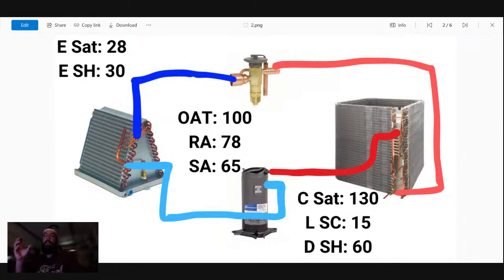It could also be some kind of trash or debris getting into it. Now we have a screen that should correct for that, but stuff still gets through. Anyway, that was the actual diagnosis. It was an underfeeding valve. You get into steps of what you do about the valve now.